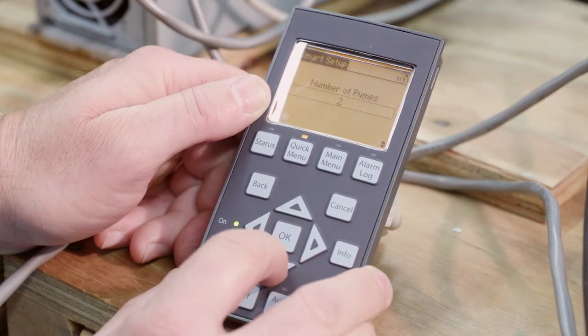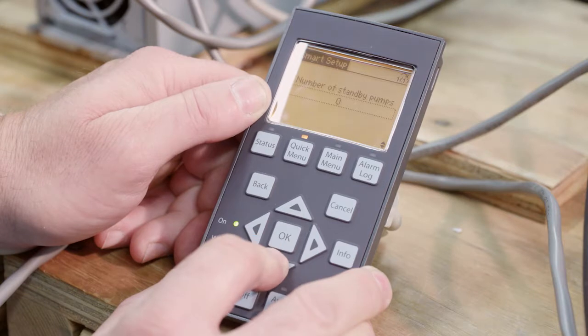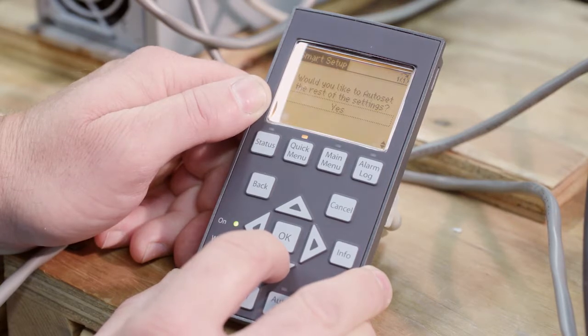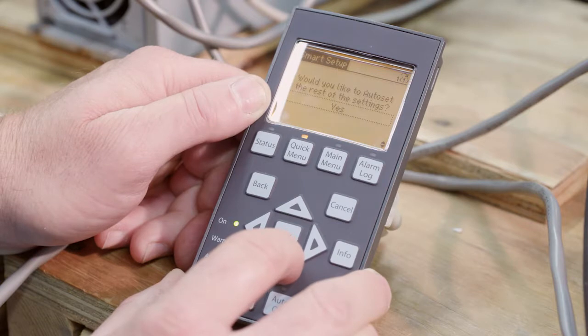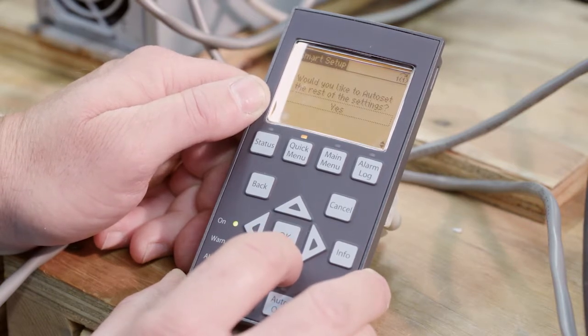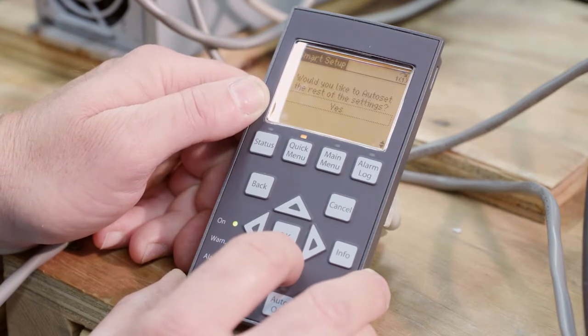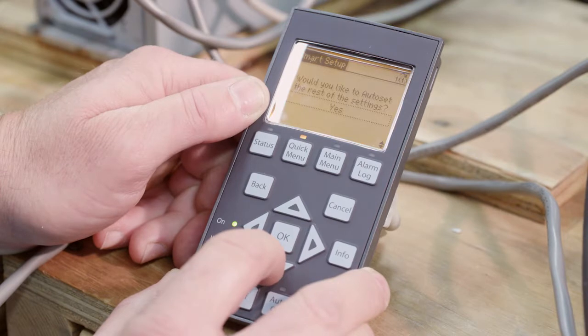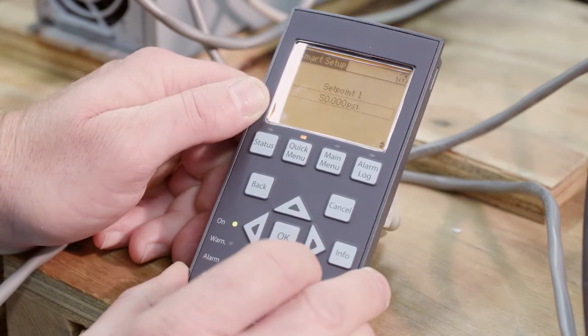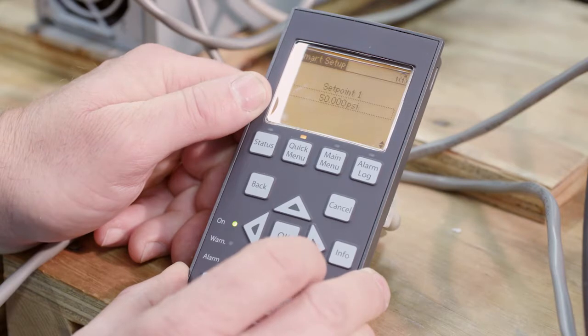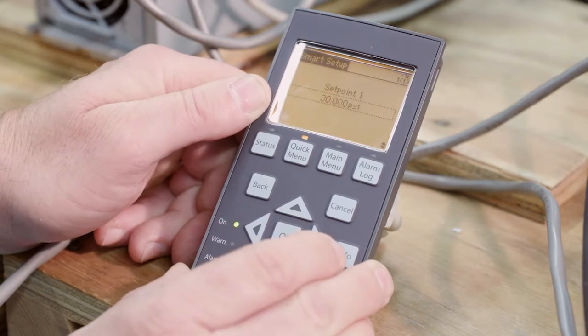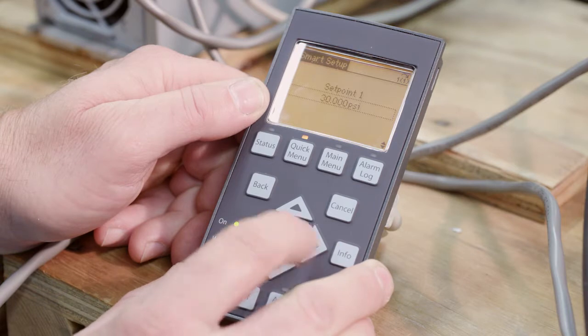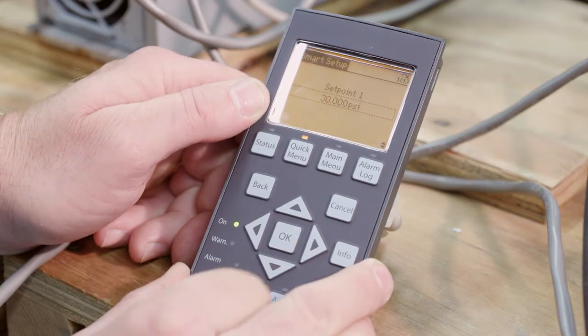So number of pumps, 2, got a duplex here. Number of standby, 0. Now, would you like to auto set the rest of the settings? So, auto set is really handy, and it just sets all kinds of parameters for you. And so in a simple basic system, this is a nice tool to have, and let the system, the IPC, set everything for you. So we're going to say yes. So set point. It's preset to 50, but let's just go ahead and make a change now to 30. So we can always go back and change any of these, and there's a new feature here that I'll show you how to change your set point. But let's set that to 30.